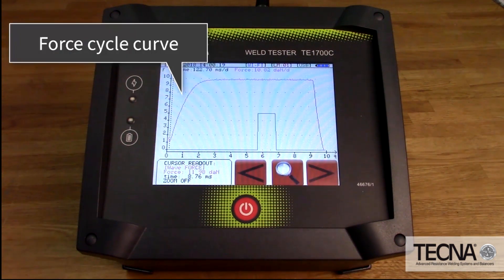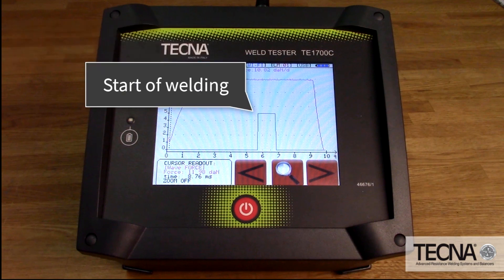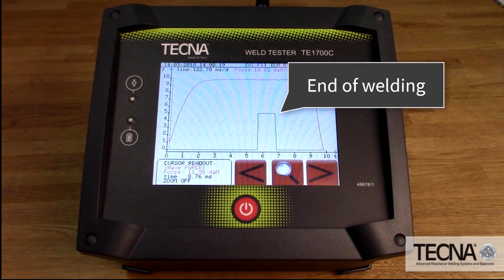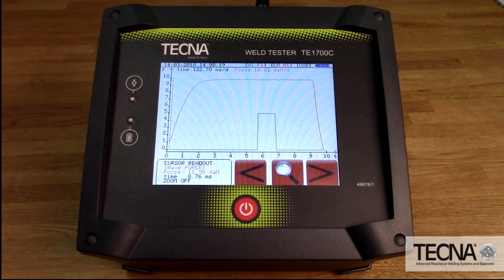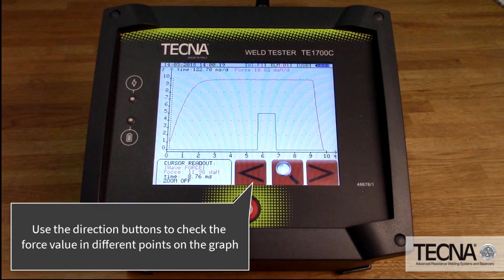You can also use the graphical display to show at what point in the force curve weld current is being turned ON and OFF. Once this value is known, squeeze time can be shortened to this point to allow maximum production speed.